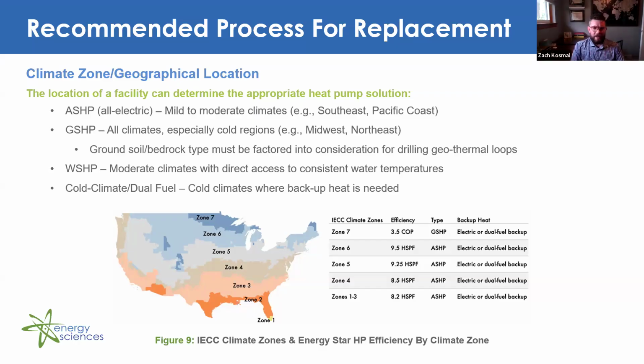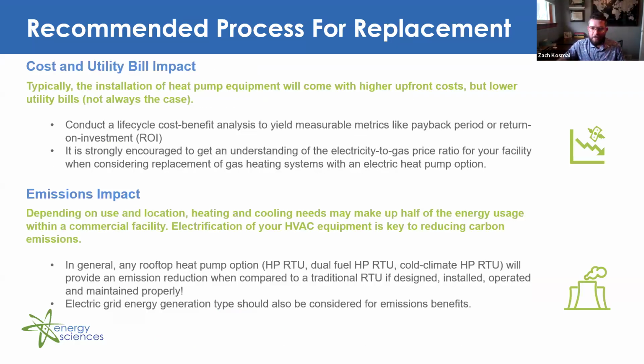And lastly, just always keep in mind that efficiency does not always imply effective operation. For example, an air source heat pump with a high COP does not imply that it'll be effective in your application. And I know I'm running short on time here, but I'll try to wrap it up as quick as I can. We've got a few more slides here.